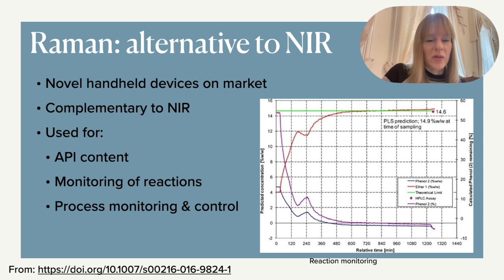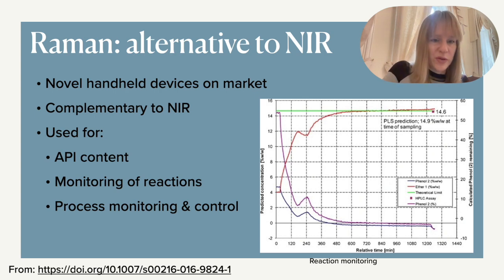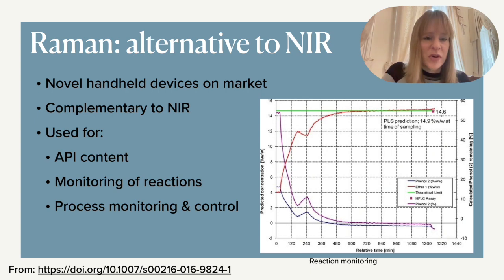Things like carbon-carbon bonds and graphene can easily be detected with Raman. Also, the OH peak of water really dominates an NIR spectrum, which is a major problem when looking online in a reactor. Raman is therefore much better suited to systems in water. Similarly to NIR, Raman can be used to determine API content, though it is slightly more expensive and therefore not as routinely used. It can monitor reactions and control certain processes — for instance, using a PLS model to predict how much product is formed over time and how much substrate is used, checking whether your reaction is running according to plan within the bioreactor.